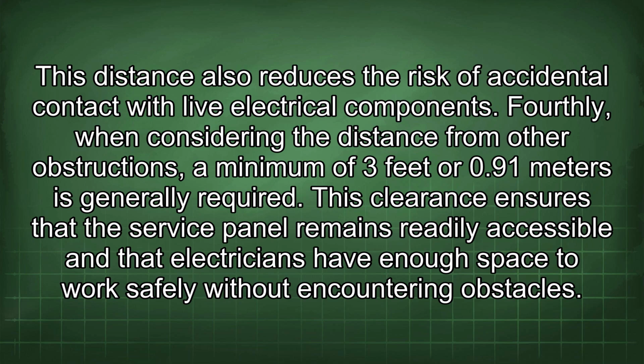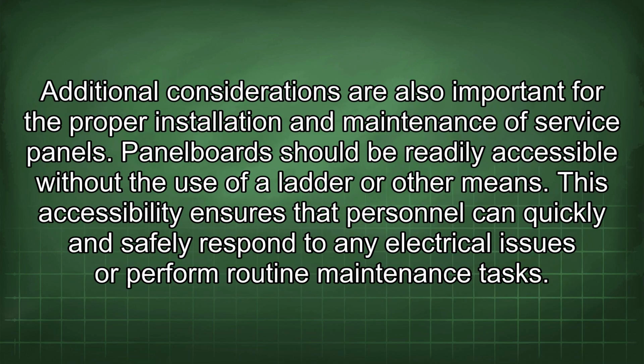Fourthly, when considering the distance from other obstructions, a minimum of 3 feet or 0.91 meters is generally required. This clearance ensures that the service panel remains readily accessible and that electricians have enough space to work safely without encountering obstacles. Additional considerations are also important for the proper installation and maintenance of service panels. Panel boards should be readily accessible without the use of a ladder or other means. This accessibility ensures that personnel can quickly and safely respond to any electrical issues or perform routine maintenance tasks.